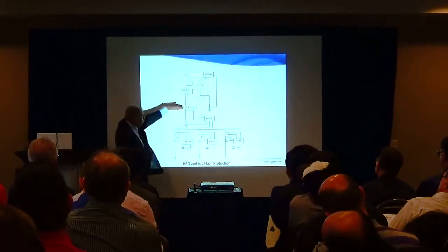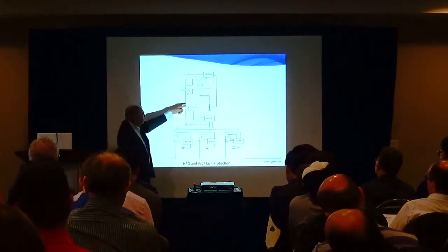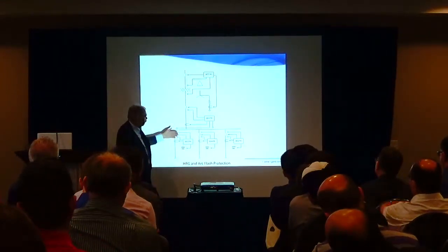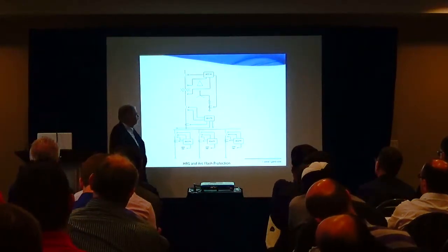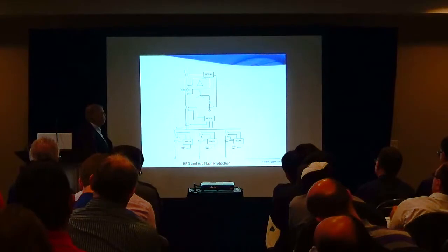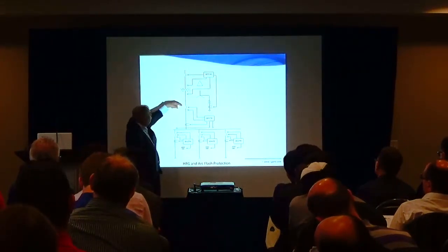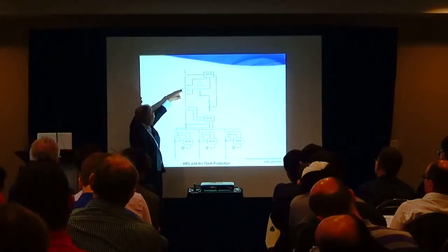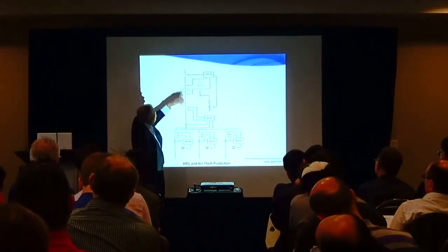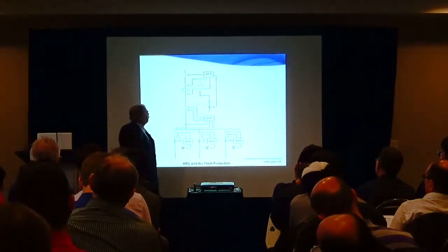I can do all my protection on the load side quite easily by applying resistance grounding, by putting in sentries and arc flash sensors and so on, and I'm good here. So when my report comes on the arc flash study, I will be less than 9 calories. But what happens on the line side? If the fault is in the terminal box, in here or here in the cable connection on the line side, then my protection is on the line side. If I have a fuse and a load break, that's not going to give me low energies.